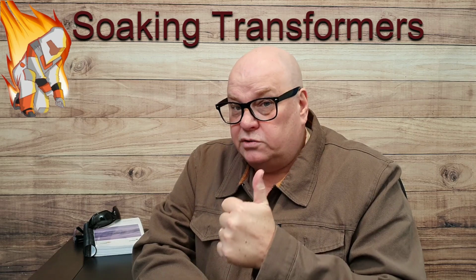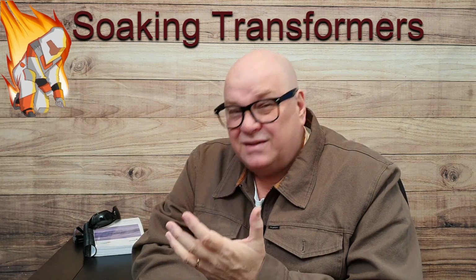But if you're curious about soaking a transformer, certainly do it on a new transformer. Some people even say that after the transformer has got to your site, it's a pretty good bet the oil is absolutely everywhere within the windings. But it's still not a bad idea. I would soak it, even if it's come from one end of Australia to the other. If it's a new transformer, I'd soak it.